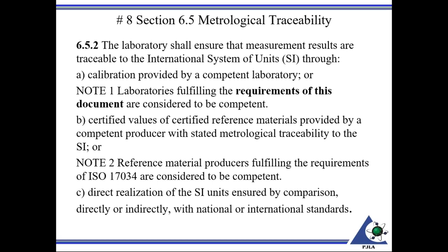Objective evidence that can support that would be a scope of accreditation. Or certified values of reference material provided by a competent producer. Again, 17034 accreditation would be objective evidence that could be presented to assure that your reference material producer that's claiming traceability is competent. There are some instances of direct realization of the SI unit, ensured by comparison directly or indirectly with national or international standards.